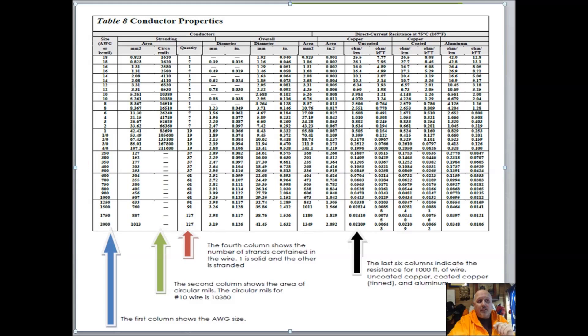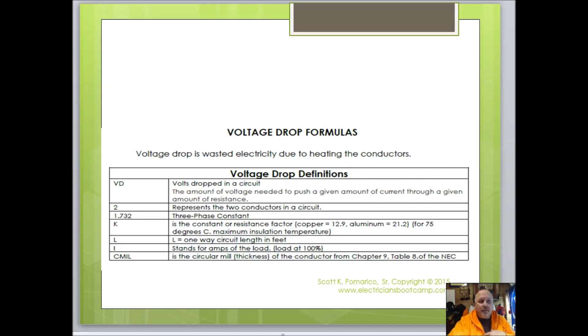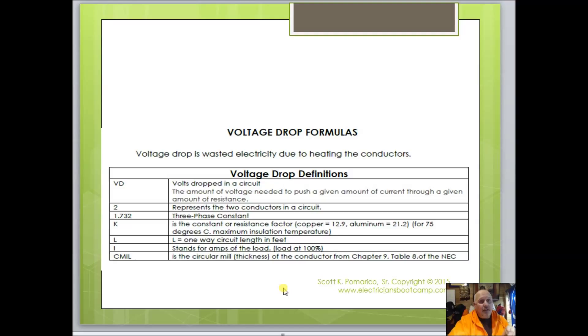Definitions: voltage drop is the push of a given amount of current through a given amount of resistance. The factor 2 is used in single-phase calculations; 1.732 (the square root of 3) is used for three-phase calculations. K will be used in our calculations — either 12.9 for copper or 21.2 for aluminum. This K factor can be used when the problem doesn't specify the wire type. Other inputs include length, ampacity at 100%, and circular mills from Table 8.